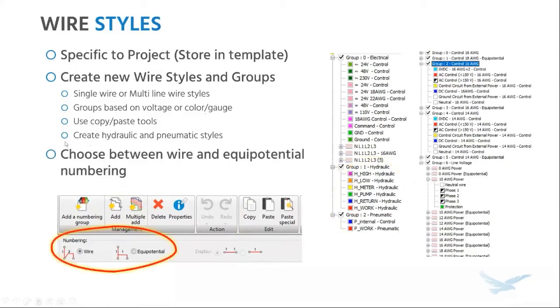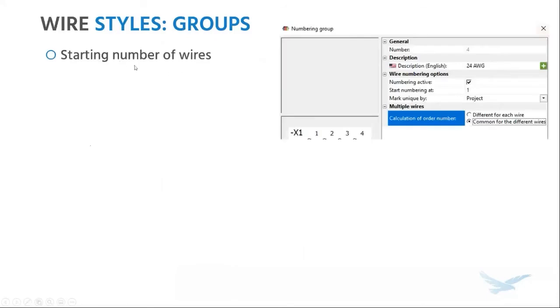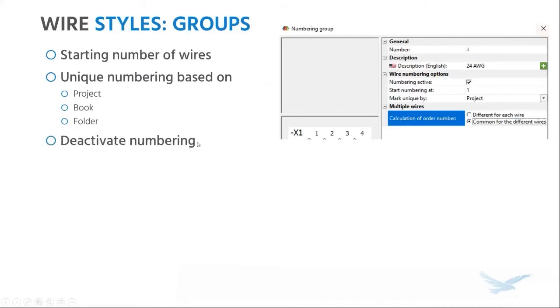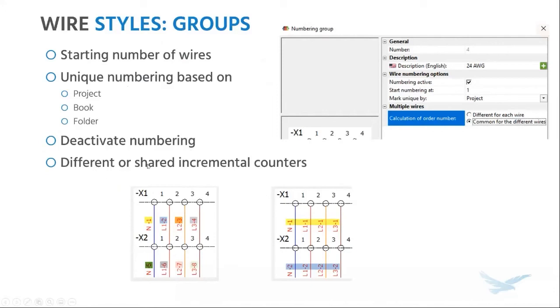You can also choose the scheme of wire numbering that you want — you can either number individual wires or have a number for every voltage potential. I mentioned groups and how you can put wire styles into those groups. Apart from being an organization tool, you can push a range of options across to all the wire styles in that group — for example, the starting number of the wire, whether you want to start numbering at one or 100, whether you want unique wire numbers across the project or the book or the folder, do you even want wire numbers, and whether you'd like different or shared incremental counters across wire styles in that group.